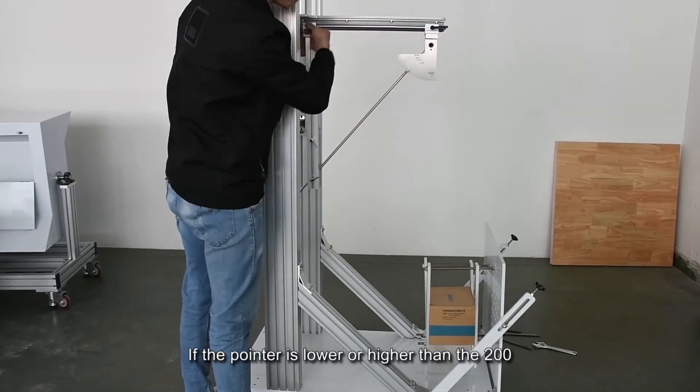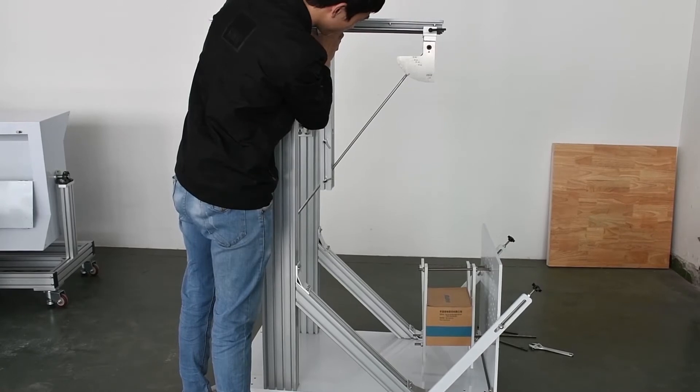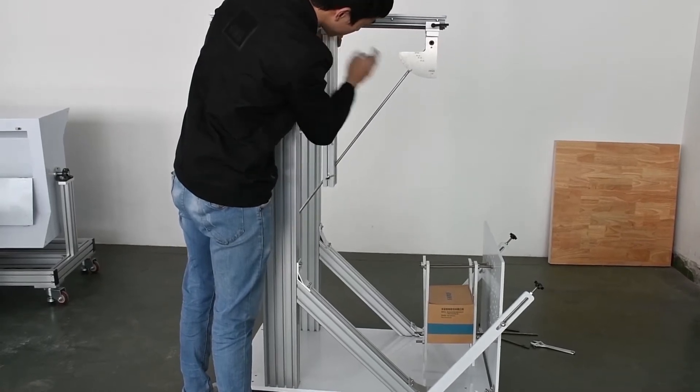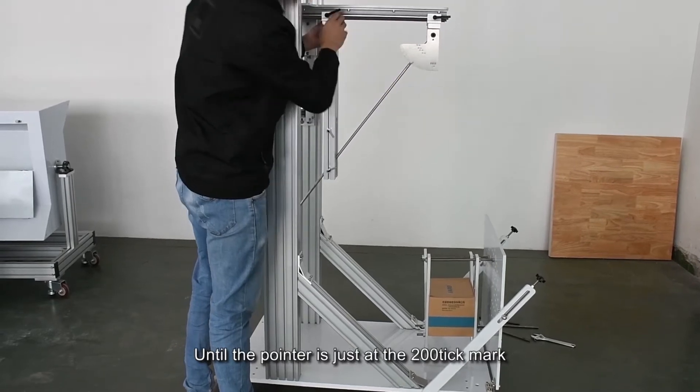If the pointer is lower or higher than the 200, we can adjust here until the pointer is just at the 200 tick mark.